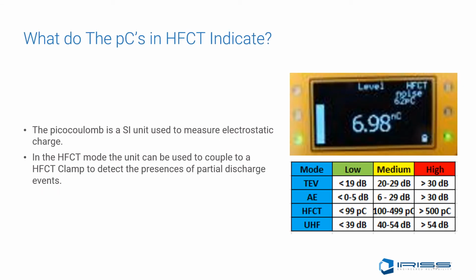What do the picocoulombs in HFCT indicate? The picocoulomb is an SI unit used to measure electrostatic charge. In the HFCT mode, the unit can be used to couple to an HFCT clamp to detect the presence of a partial discharge event. If a unit is receiving less than 99 picocoulombs, this anomaly would be rated low on the alert action report. Between 100 to 499 picocoulombs, this would be a medium alert on the action report, and 500 picocoulombs or greater would be a high alert for the action report.